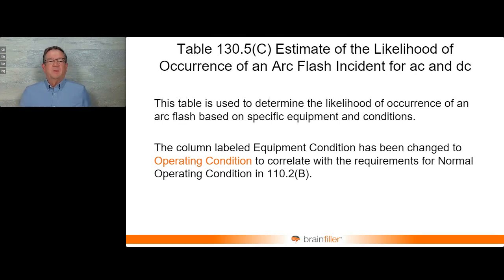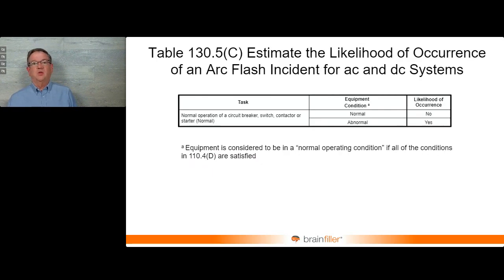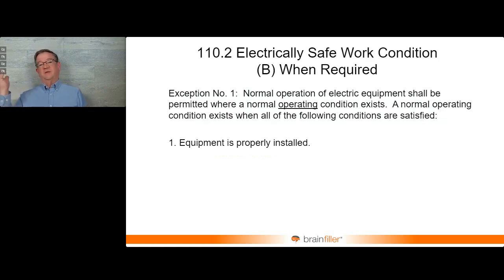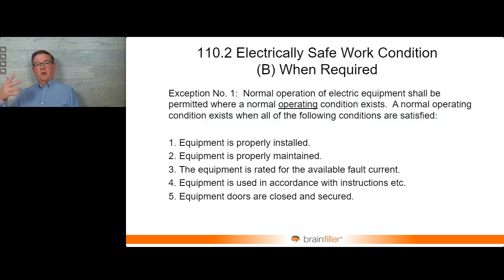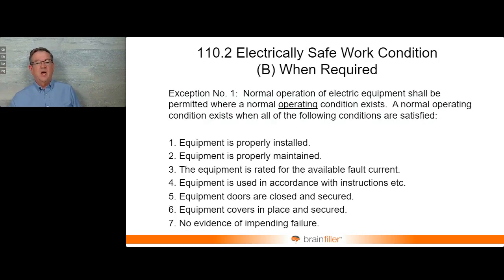So, some other things I want to look at here, estimating the likelihood of an arc flash. There's a table for this, and there's a change made just to the terminology. Instead of equipment condition, which is the middle column, that was changed to operating condition to sync up with other terminology within 70E. And it references the 7 boxes to check. Was the equipment properly installed, properly maintained? But it's just terminology, just to get it to sync up with everything else.